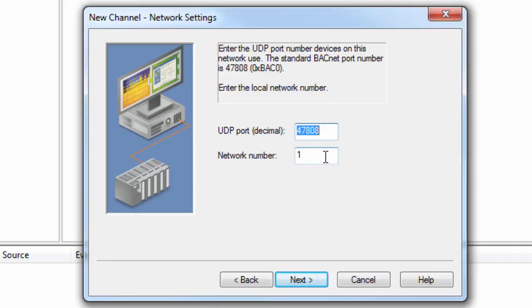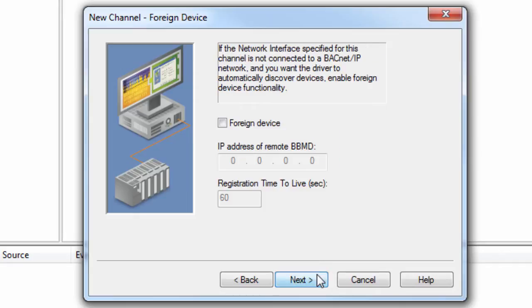Click Next to set the Foreign Device settings. A foreign device is a BACnet IP device or software application that resides on an IP subnet that is not part of a BACnet IP network. BACnet IP subnets are considered part of a larger BACnet IP network if both directed and broadcasted messages can be forwarded to and from the other subnets by IP routers and BACnet broadcast management devices.